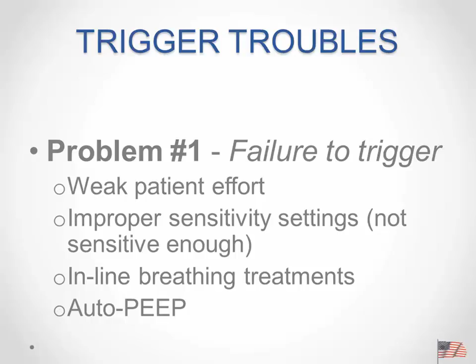All right, so since we know all about triggers in a different way, we can trigger the ventilator. How do we know when it's not working correctly? The two major problems you'll run across are a failure to activate the inspiratory phase when the patient's effort is there, and auto-triggering. Some of you experienced that when you were breathing on the ventilator and it had a really poor trigger setting. So, failure to trigger could be any one of these. So let's talk about them.